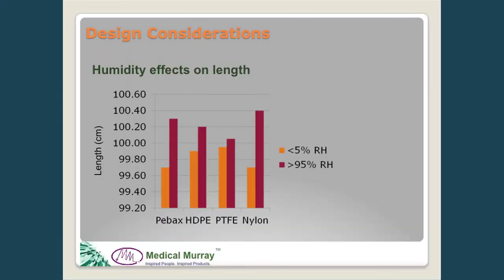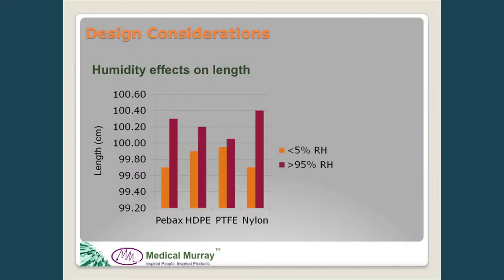A third consideration that can sometimes be overlooked is the effects of moisture absorption in plastics, or the effects of humidity on length. This is critical for devices where we need to advance one component from the tip a specified length. If components are made of dissimilar materials, depending on the environment they're stored in, we can have a different result after a set period of exposure to a more or less humid environment.